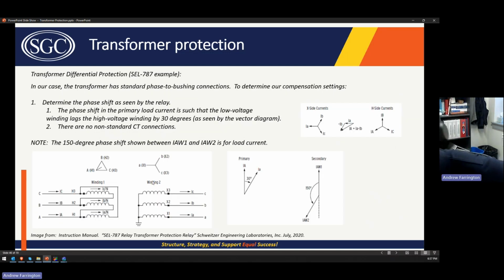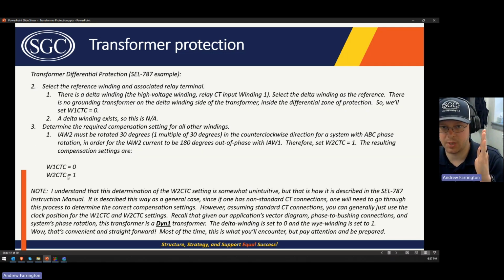That's confusing to me. I'm going to say that in 99% of applications that you're going to run into where you have a delta Y transformer with standard CT connections and a standard transformer phasing of either DY1 or DY11, what you just need to do is set the delta winding to 0 and then set the Y winding to the clock position that corresponds to the phase shift for the transformer. So in our case, it would be 1. So you can see that that results in the same answer.